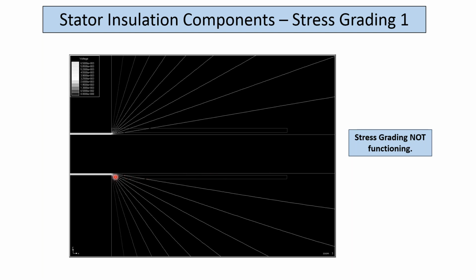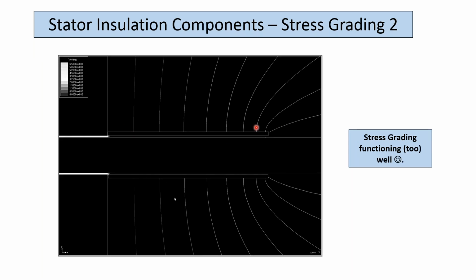Okay. So this is the stress grading. If the stress grading doesn't work, you've got air here, and you've got a very high electric field in air, and that's enough to cause ionization and glow discharge and all sorts of things that would damage the insulation over time. So that is the purpose. The stress grading is to grade these voltage lines out so that you spread the voltage in air.